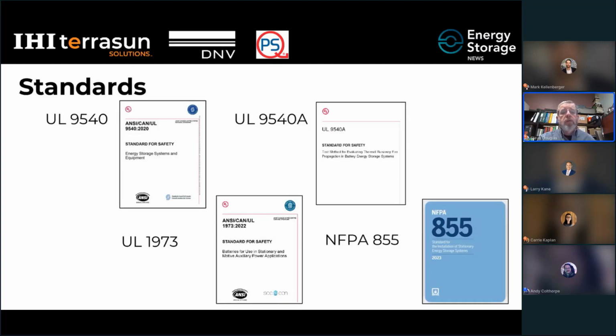The standards used for energy storage systems, as mentioned before by Larry, include UL 9540, the main standard for energy storage systems for both US and Canada. Next is UL 9540A, which Carrie mentioned, covering thermal runaway testing for energy storage systems. UL 1973 is the test standard for the batteries themselves. And NFPA 855, as Larry mentioned, is the installation standard used in the US.